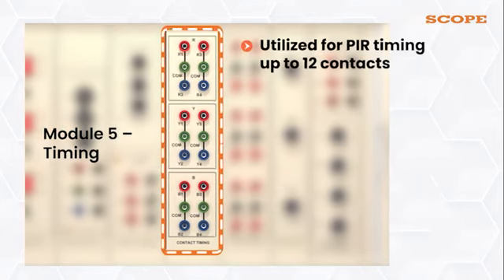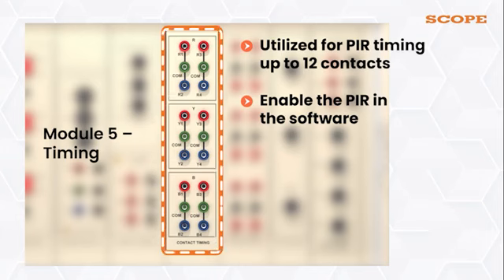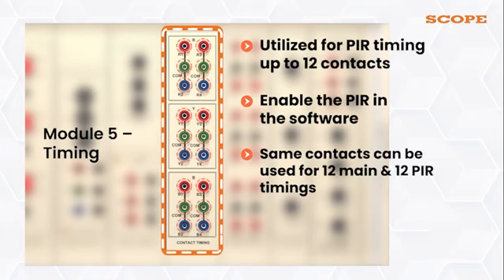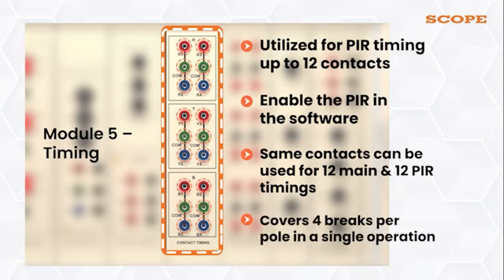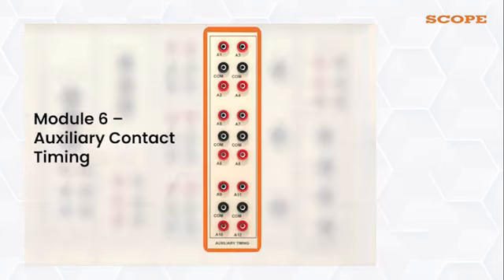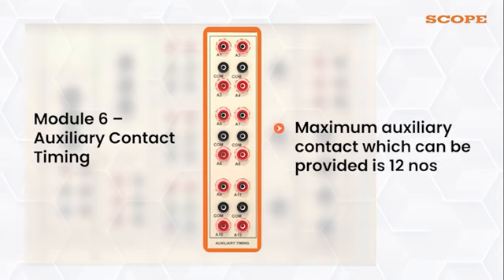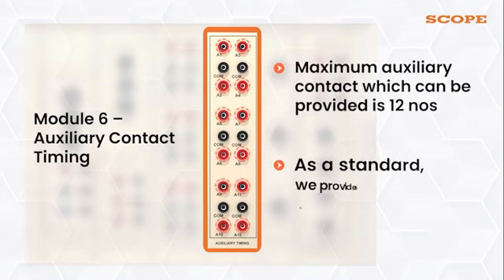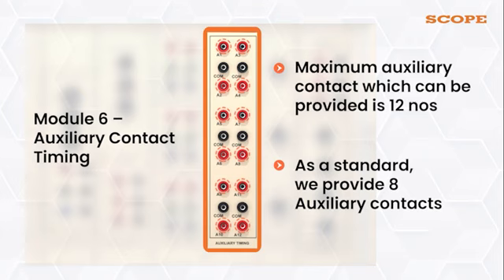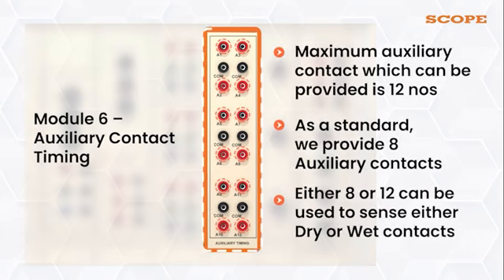The same is utilized for PIR timing up to 12 contacts, for which you need to enable the PIR in the software. Thus the same contacts can be used for 12 main and 12 PIR timings, which covers 4 breaks per pole in a single operation. Module 6. Auxiliary Contact Timing Module. The maximum auxiliary contact which can be provided is 12 numbers as shown in the figure beside. As a standard, we provide 8 auxiliary contacts. Either 8 or 12 can be used to sense either dry or wet contacts.